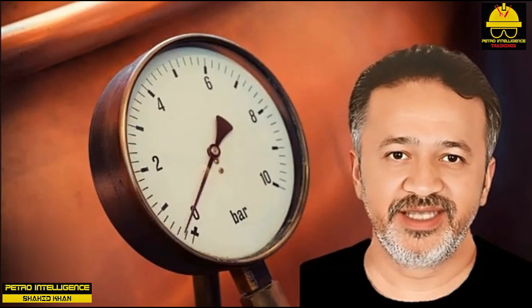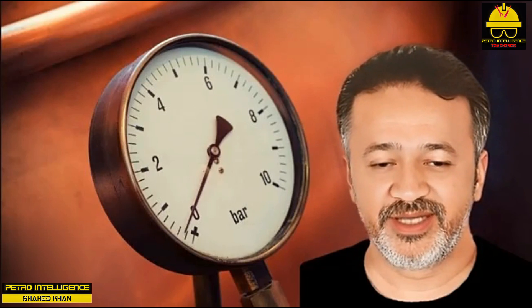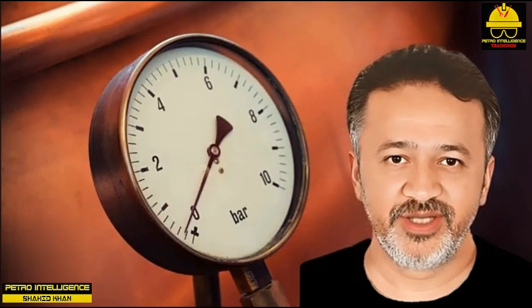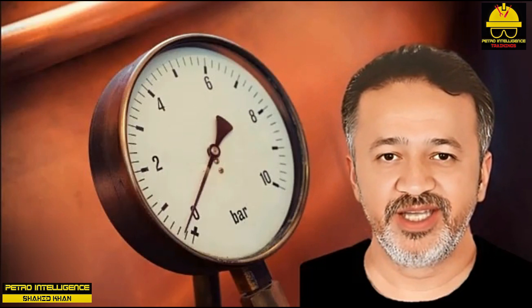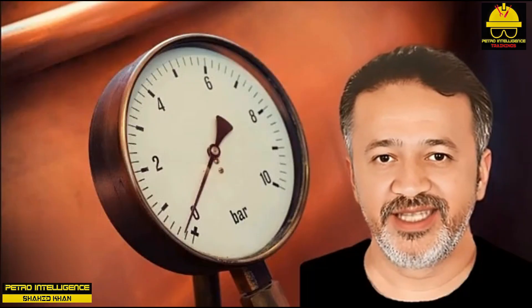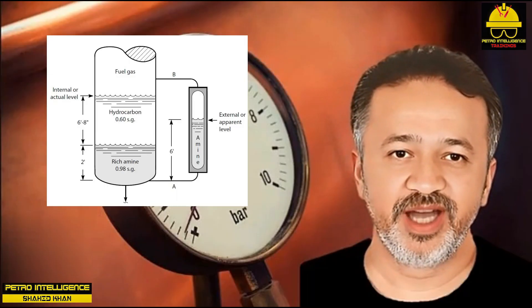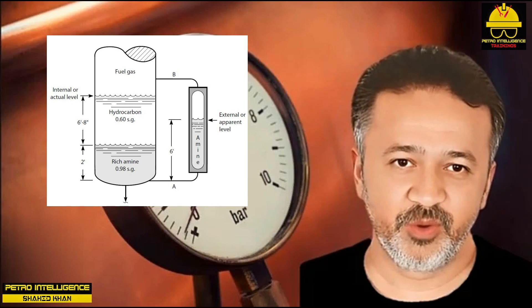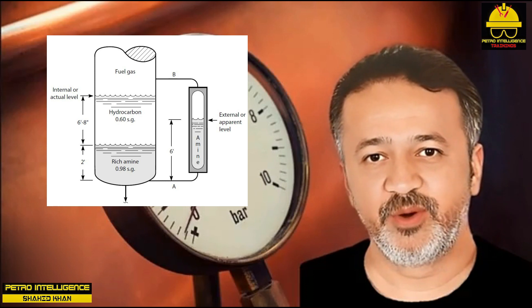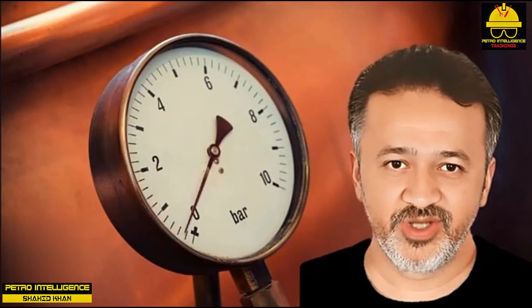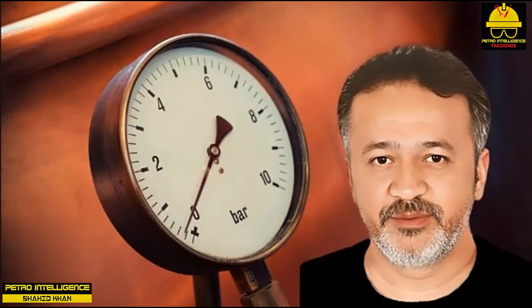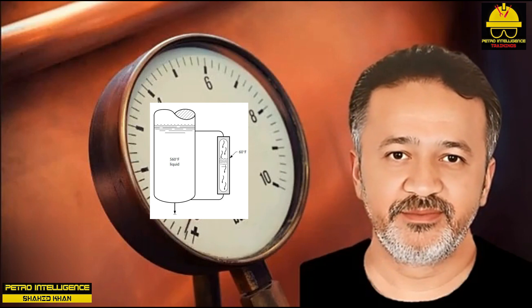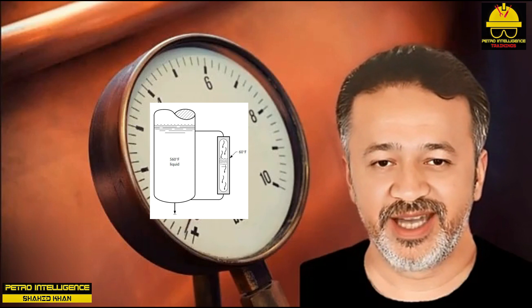For example, suppose the height of hydrocarbon liquid in a gauge glass is four feet between the level taps, the glass temperature is 60°F, and the tower temperature is 560°F. The temperature difference is 500°F. Applying the rule: 500 × 5 ÷ 100 = 25%, meaning the liquid in the gauge glass is 25% denser than in the tower. Therefore the liquid level in the tower above the bottom tap is (1 + 25/100) × 4 = 5 feet — the tower liquid is one foot above the level shown in the glass.